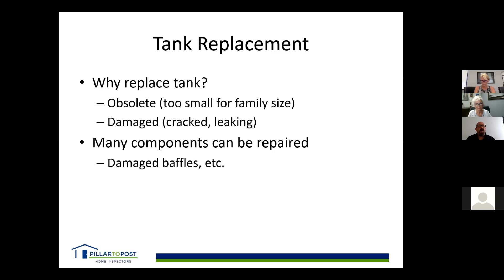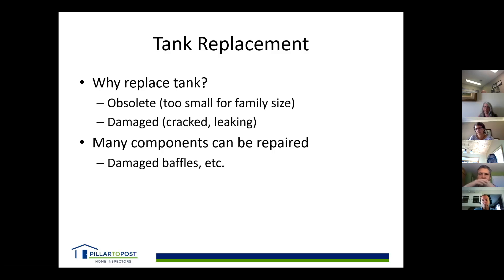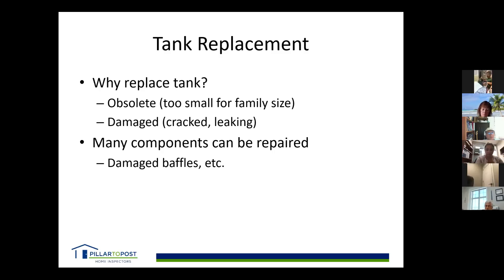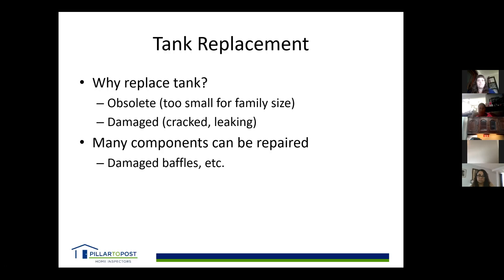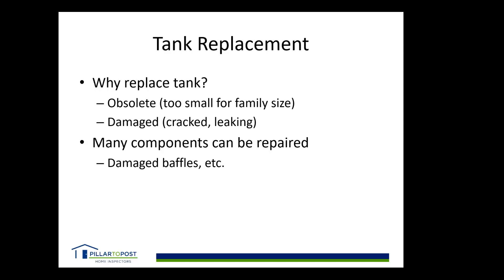Why would you ever have to worry about tank size in an existing house? If a house had two people and you're moving a family of six in, the tank is now too small. Adding an extra bathroom or doing additions on a house — the septic tank is designed for a certain load, and more water going in means it's too small. House additions are when tanks typically need to be replaced.